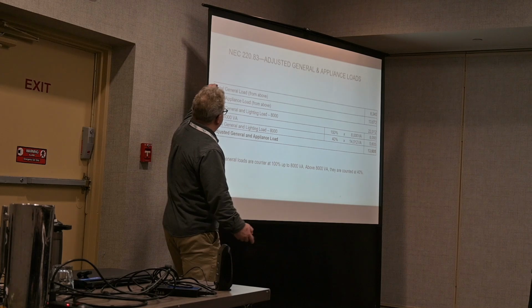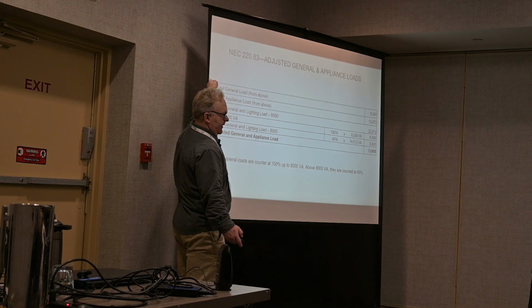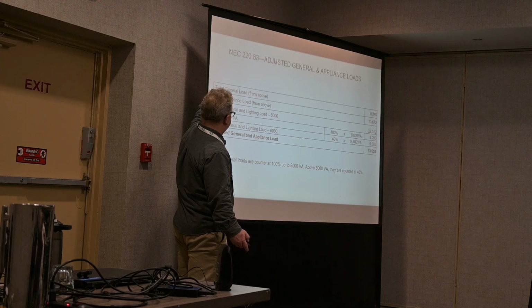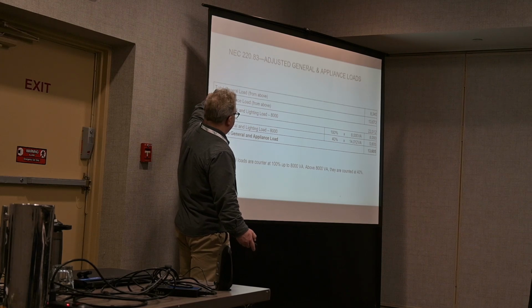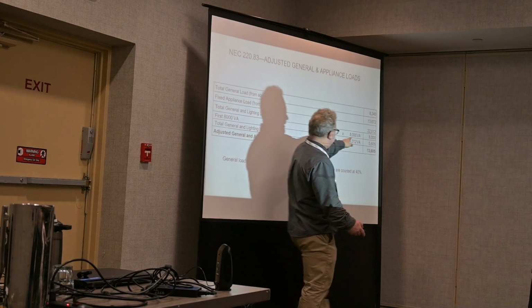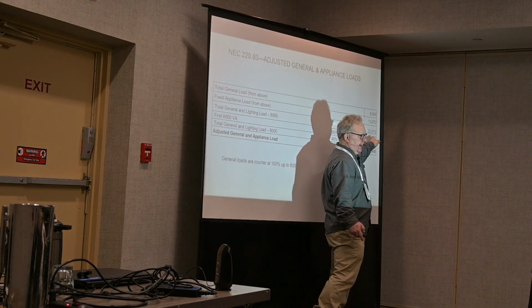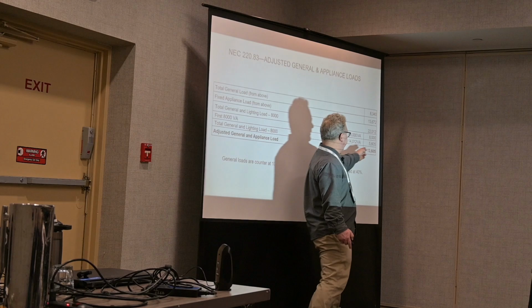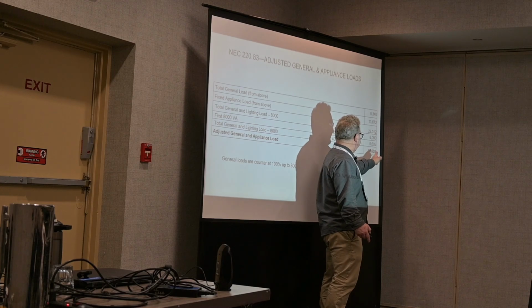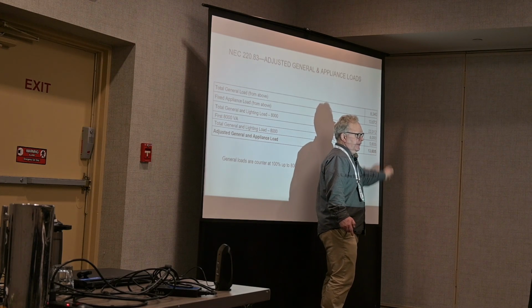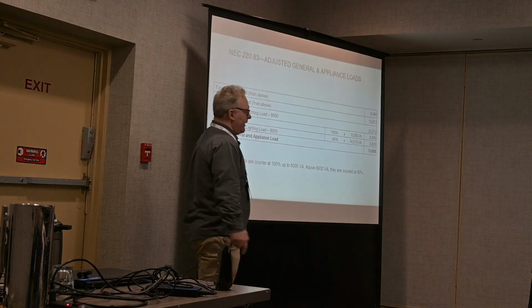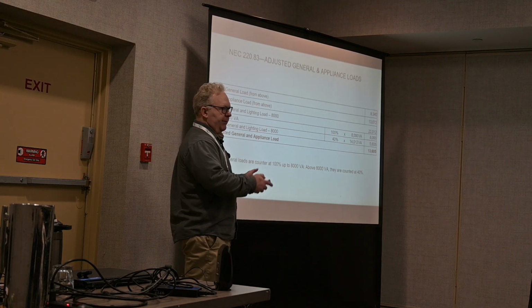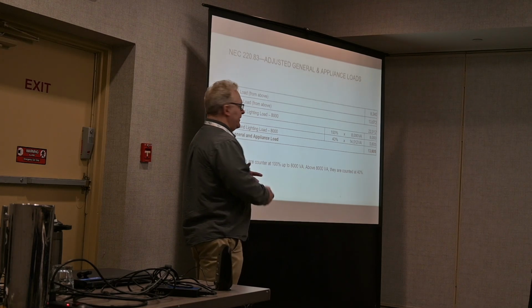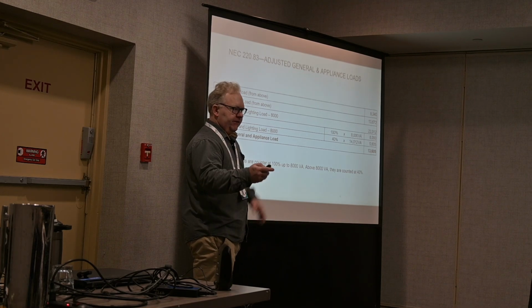And now we add up our general loads based on our square footage and our small appliance branch circuits and our fixed appliance loads. And of this 22,000 VA, we take the first 8,000 at 100%. And then anything above that, we only count at 40%. So even though when we add all this stuff up, it comes to 22,000, after the adjustment, it's only 13,600. So one of the take-homes of this is that while it's really important to count up all these appliances, they don't count as much towards your total as HVAC loads.